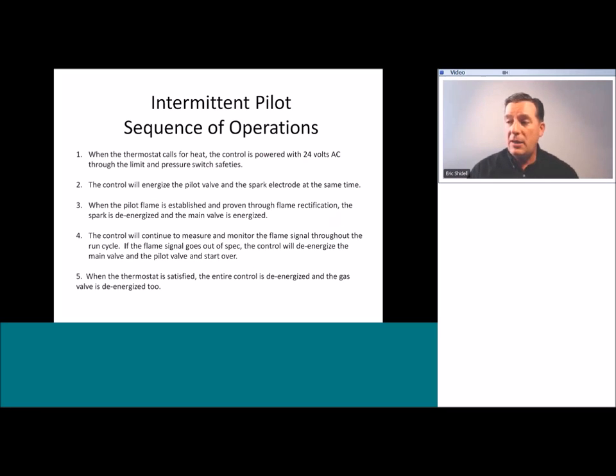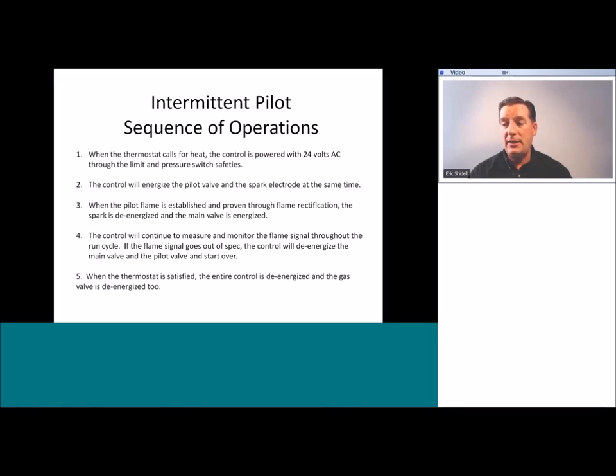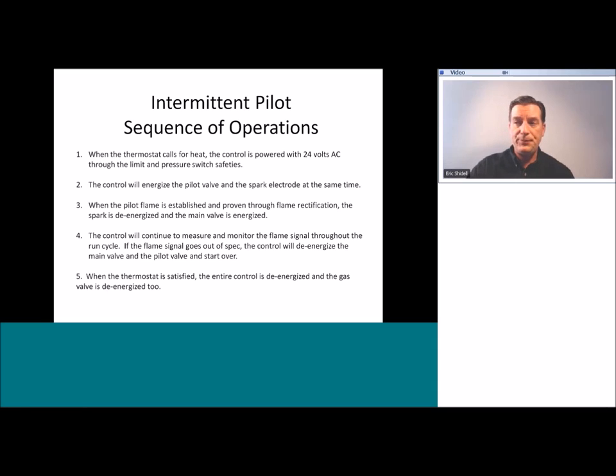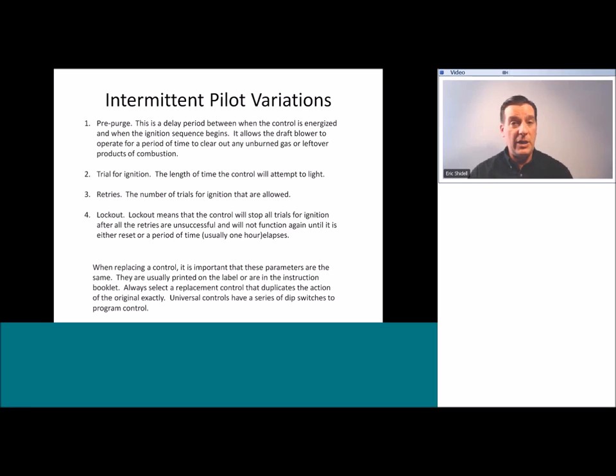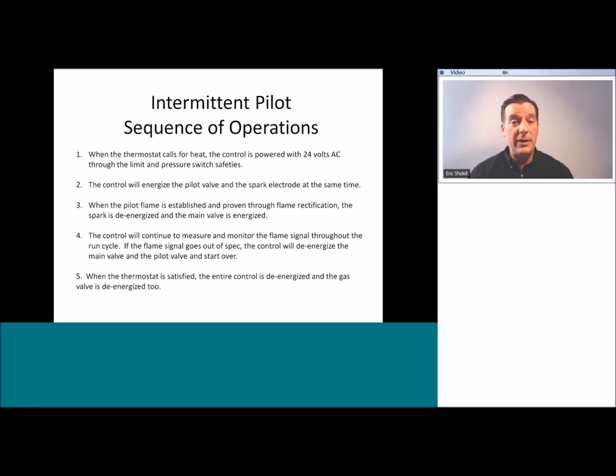Here is the basic sequence of operations for an intermittent pilot control: when the thermostat calls for heat, the control is powered with 24 volts AC through the limit and pressure switch safeties. The control energizes the pilot valve and spark electrode simultaneously. When the pilot flame is established and proven through flame rectification, the spark is de-energized and the main valve is energized. The control continues to measure and monitor the flame signal throughout the run cycle. If the flame signal goes out of specification, it de-energizes the main valve and pilot valve and starts over. When the thermostat is satisfied, the entire control is de-energized and therefore the gas valve is de-energized also.